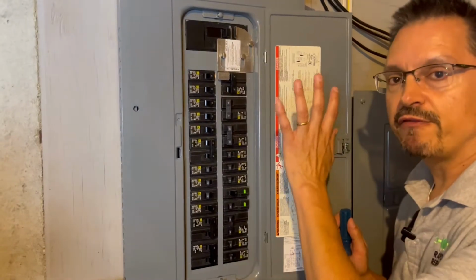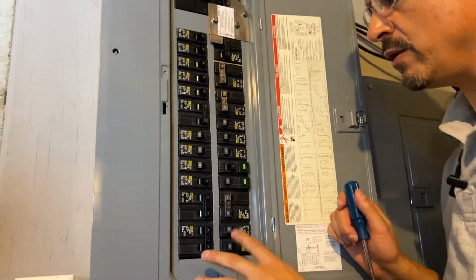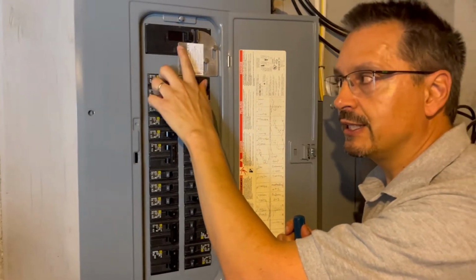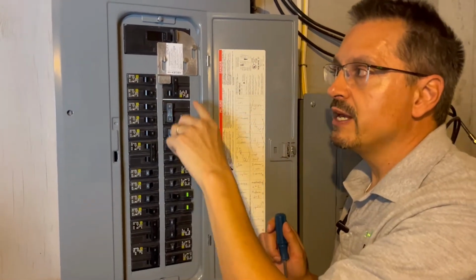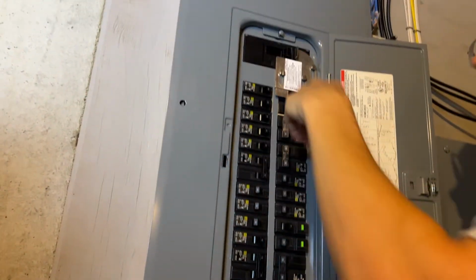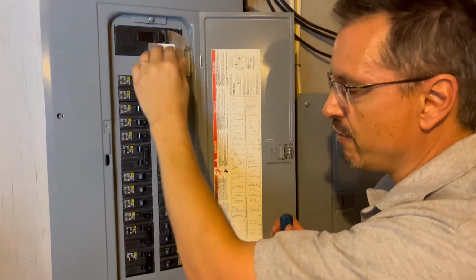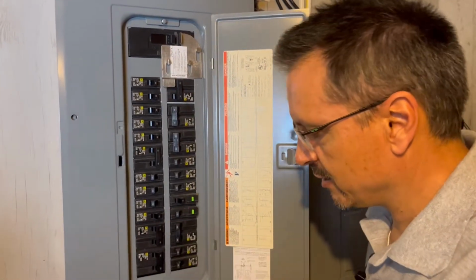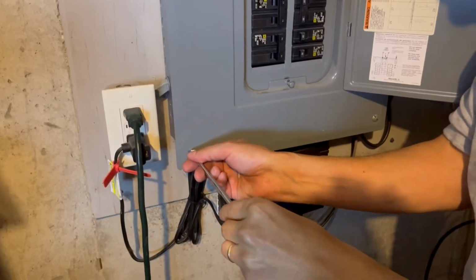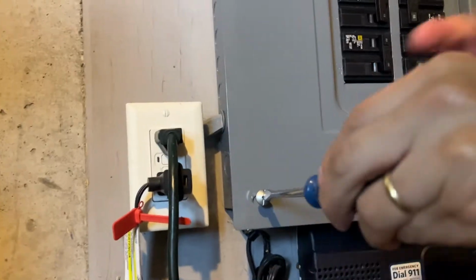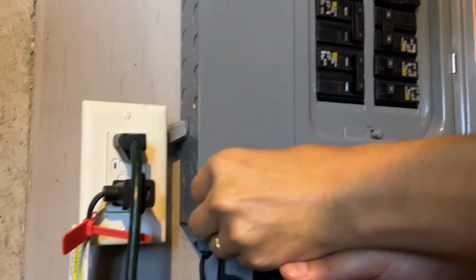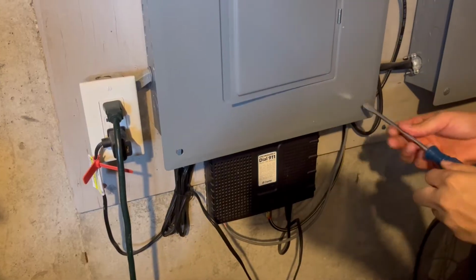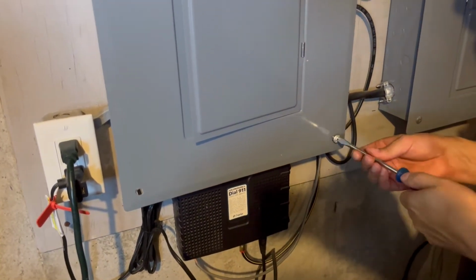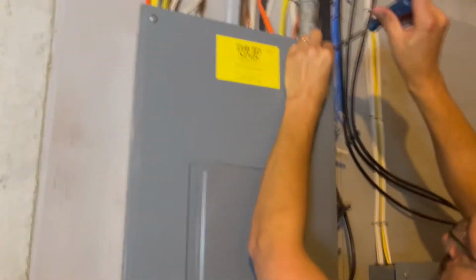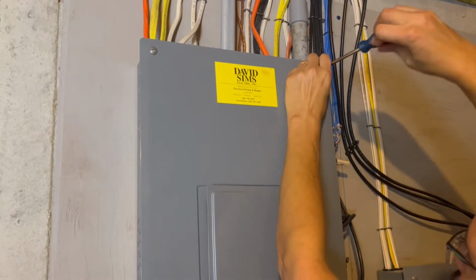First, you want to turn off the main power before you open your panel. The main shutoff can be built right into the panel like this, or you may have it remotely. If it's on the outside, remotely turn that off, or you can turn off the panel here and everything below that will be off. I'll show you when we get to the inside. Now, safety, when working inside electrical panels, you should have your arms covered. In a perfect world, maybe a cotton long sleeve t-shirt. You could actually put on eye protection. You can use a voltage detector to make sure you do have the power off.